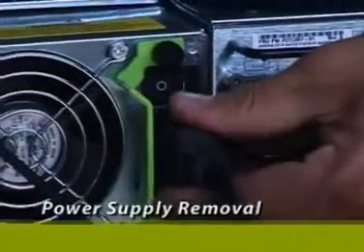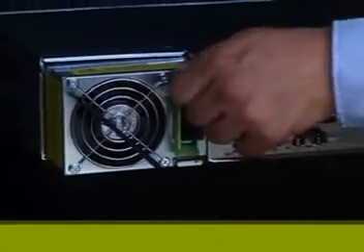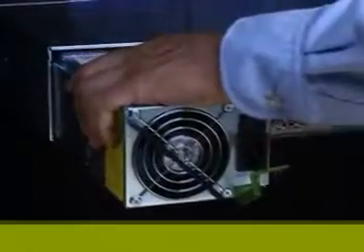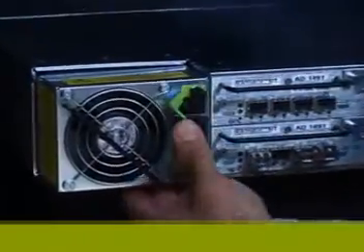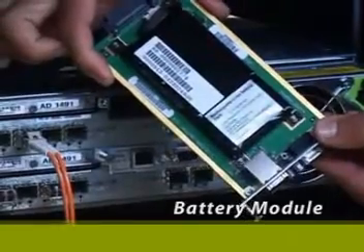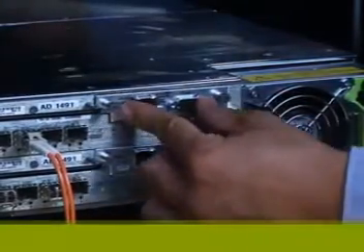All StorEdge 3000 family arrays have two hot-swappable power supplies that can operate on either 90 to 265 volts AC or negative 36 to negative 72 volts DC. Both power supplies must be configured for either AC or DC operation. The battery module is fully redundant and provides up to 72 hours of power to onboard cache in the event of a power loss.